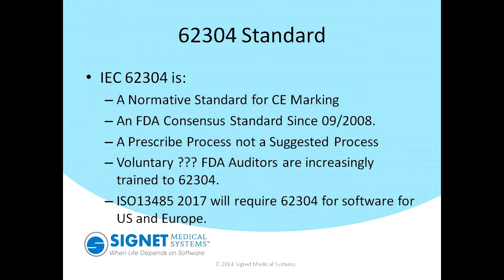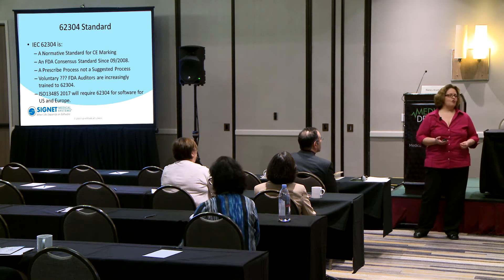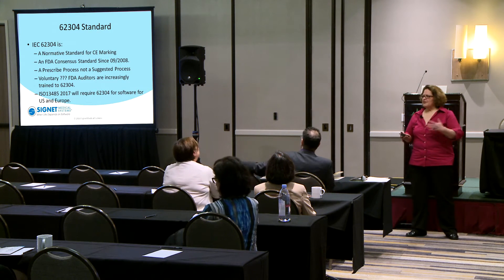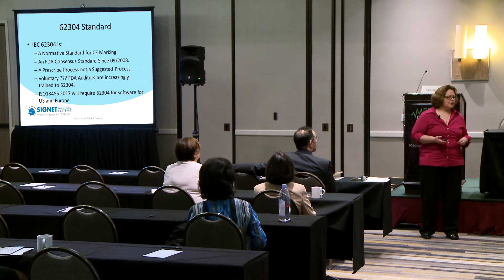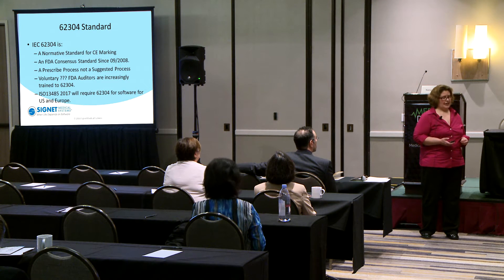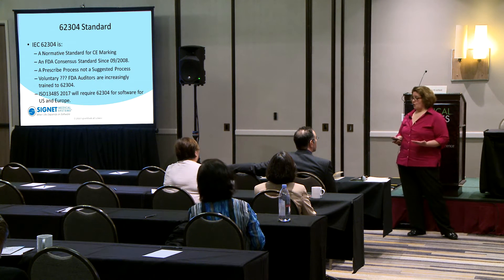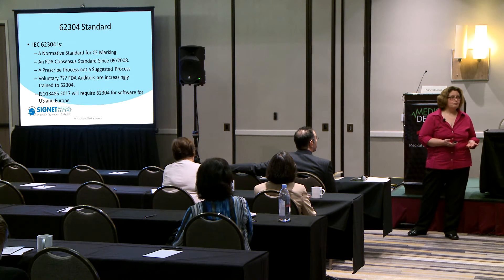62304 is a normative standard — it's European, it's US, and you'll actually see it in China. I've done submittals in China and they're more interested in 62304 than the US is. If you're doing a submittal to China and you're not 62304 compliant, you will not be able to do that. Many people ask where 62304 came from — it's been around since 2008, though the FDA wasn't particularly focused on it until around 2011. Their auditors are now being trained on 62304 and that's what they're looking for.